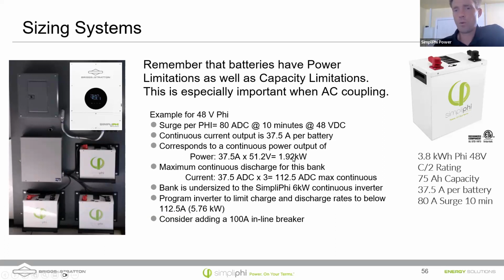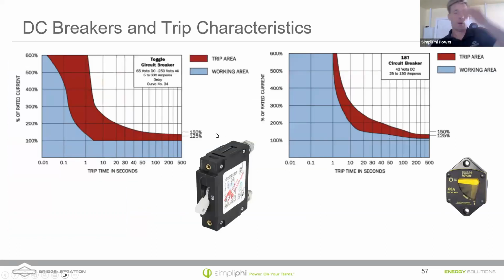So make sure to use the appropriate number of batteries for the equipment. So this is a 6 kilowatt unit. We get about 1.9 kilowatts for each battery, slightly undersized. But if you use communicating batteries, this would be okay. All right, so you can limit the equipment as well.